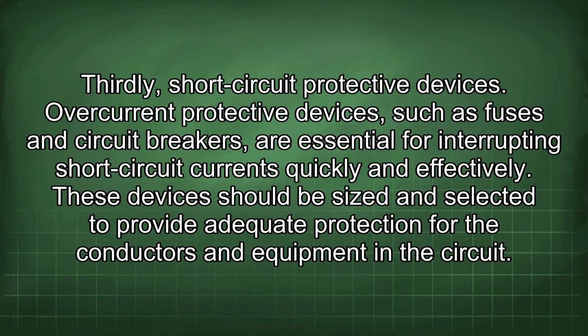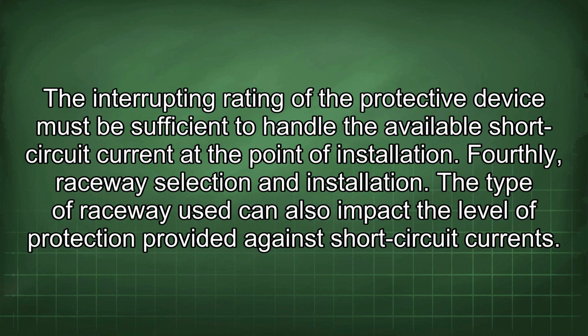Thirdly, short-circuit protective devices. Overcurrent protective devices, such as fuses and circuit breakers, are essential for interrupting short-circuit currents quickly and effectively. These devices should be sized and selected to provide adequate protection for the conductors and equipment in the circuit. The interrupting rating of the protective device must be sufficient to handle the available short-circuit current at the point of installation.